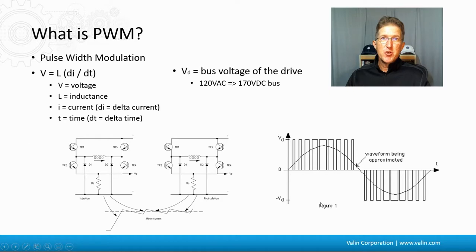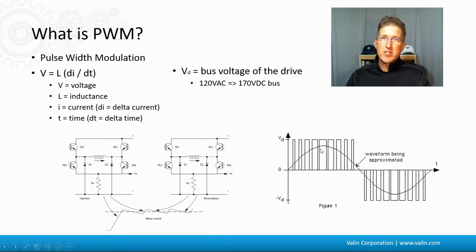A lot of people make the mistake of troubleshooting a drive and motor problem by putting a multimeter between the motor and drive to see what the voltage is. But the voltage is constantly changing from 170 to zero to negative 170, so they get some weird reading. You can see that voltage if you put an oscilloscope on there, but that's not what you want to look at. If you're troubleshooting between a motor and drive, put a current clamp on there and look at the current as it's changing. If the motor is not moving, you're stuck at whatever that current is at that location.